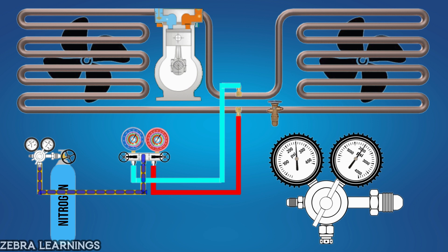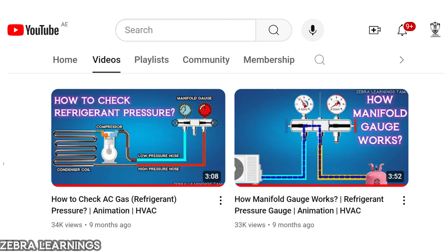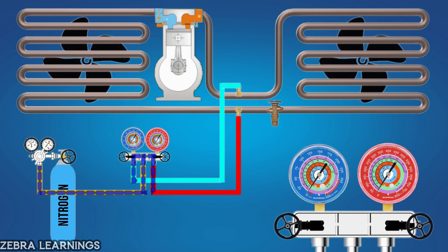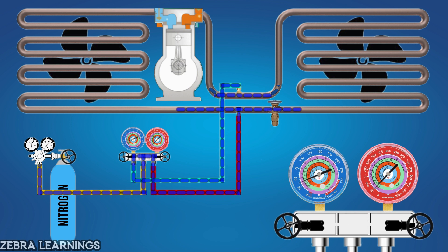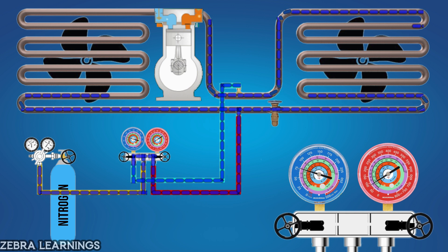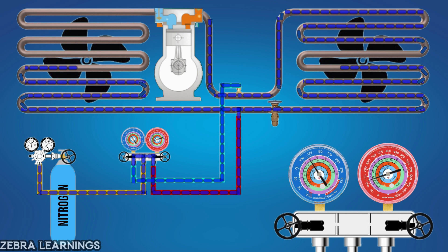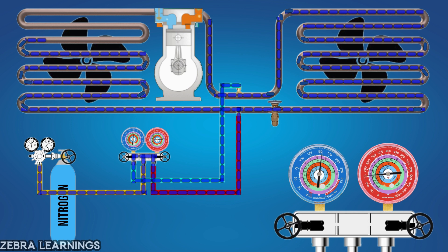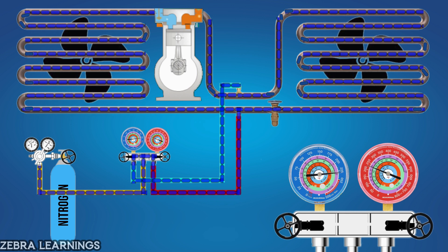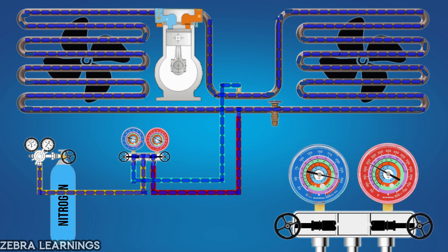Now slowly open the valves on the blue and red hoses of the manifold gauge. We have uploaded a video on our channel explaining how the manifold gauge works — the link is in the description below. Once the valve is open, it will take only a few seconds for the pressure in the AC unit to reach 250 psi. Once the pressure gauge indicates 250 psi, close the valves on the red and blue hoses. The AC unit is now pressurized with nitrogen gas at 250 psi.